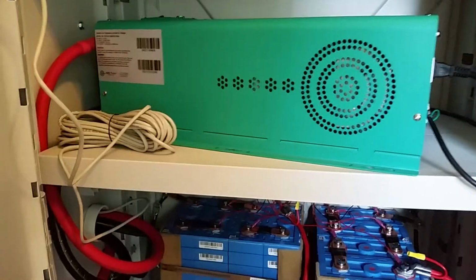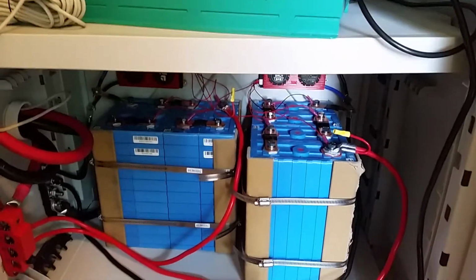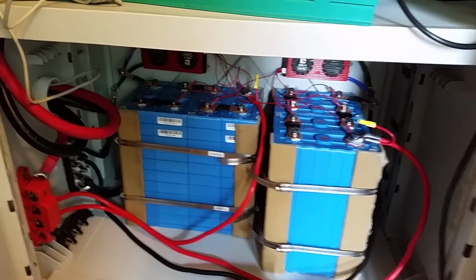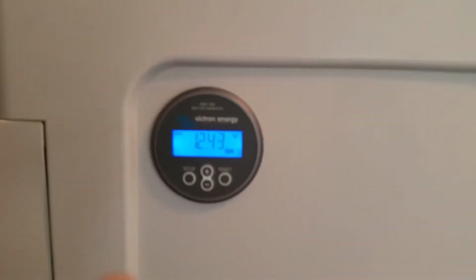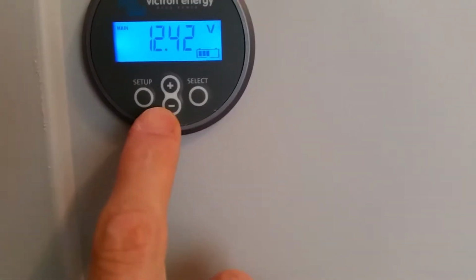Just so you know, that's probably where some of the heat's coming from, is that wattage loss there. But wanted to update you on that as well. And I did check the voltage on this battery meter with this voltmeter, and it's 1/100th of a volt difference. So what this is reading is pretty close to what this is. Just so you're aware, because I was using this to measure at the batteries and at the inverter. I'll update you on that as well. Stay tuned.